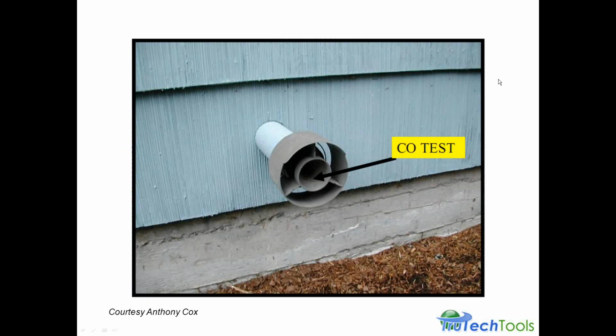Here's a picture of a high efficiency system, a condensing furnace, where you'd have to do the CO test in this type of vent. And at this point, the efficiency numbers would be pretty meaningless. You can't use them because they're too far away from the heat exchanger. Remember we talked about the thermal efficiency being a factor there, measuring near the heat exchanger. Here you've had too much temperature drop, but you could measure that oxygen level and get an idea about efficiency, and definitely the CO level, how much CO is present, could be measured at this point.